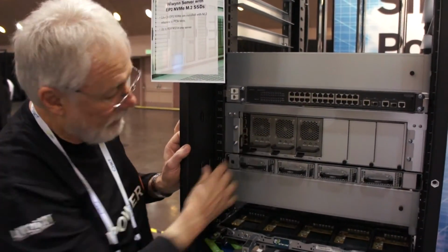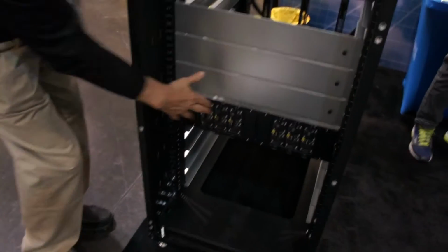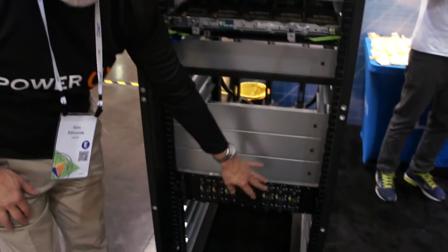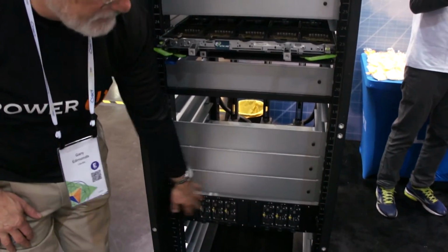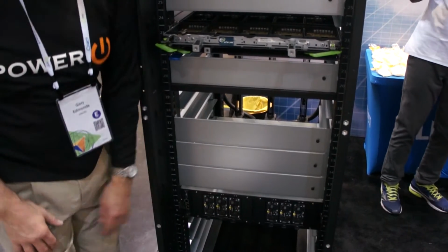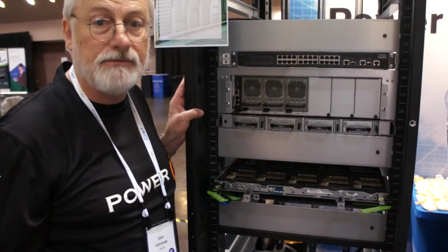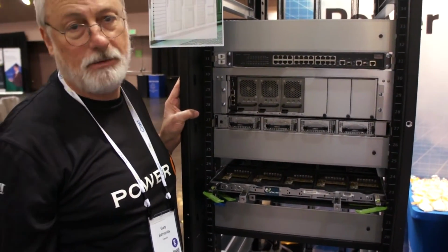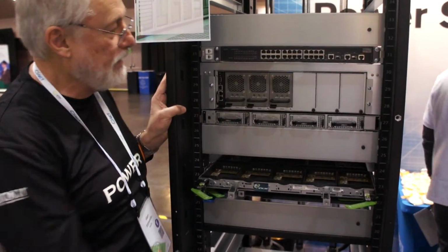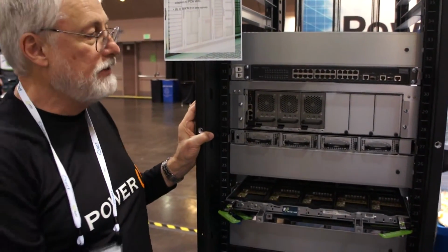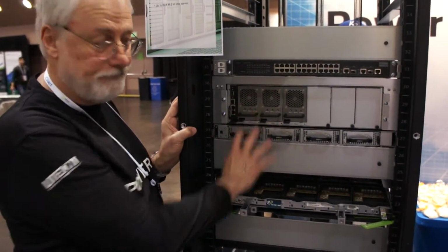Okay? And then if we go down to this one, this is just a different implementation. It, again, is a 2.5 kilowatt power supply, but these are single input power supplies, and we have up to 10 slots. So that would give you, in an N+1 configuration, 22.5 kilowatts of capability. So we can go with a medium amount of power or higher power levels, whatever the application has. So this is part of the LiteOn power offering.